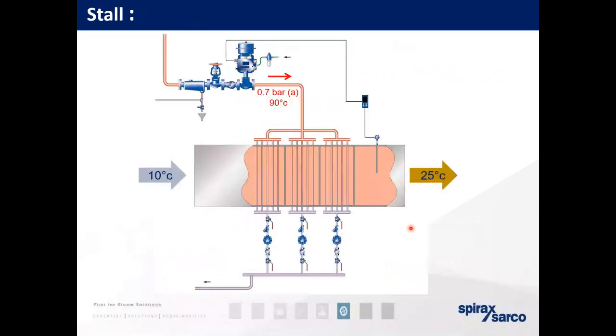So what you can find is, if you have a short area here, let's say this is only 30-40 centimeters, you can have a filling up of condensate behind the trap because it's trying to clear it. And that then leads to different heat transfer rates. So you may not reach 25°C here. The way we can do this on this particular one, if this air vent is, say, up by the ceiling, is to move these traps as close to the floor as possible. So you increase the distance here. By doing that, you increase the head pressure above the traps, and you will effectively keep the inlet pressure higher than your outlet pressure and allow the traps to work and clear the condensate.